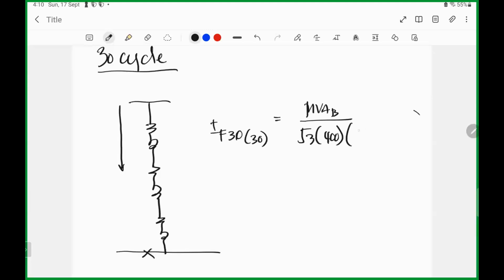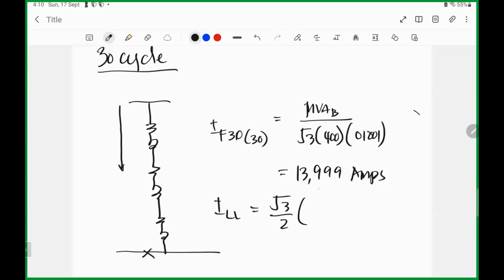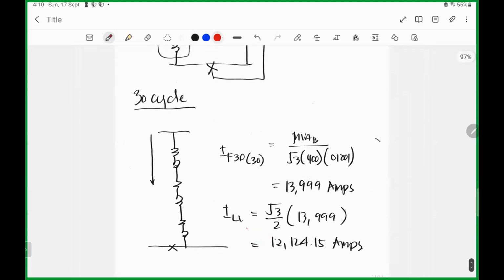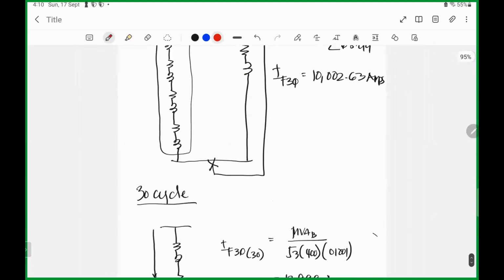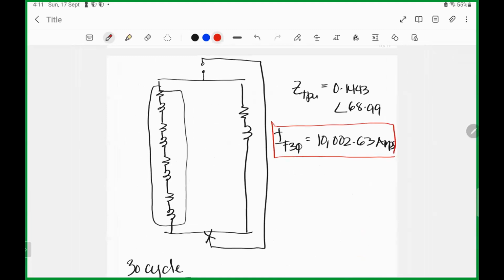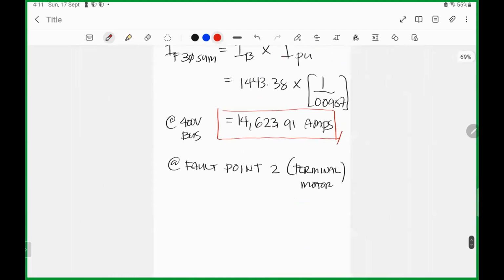Now, my total impedance will be now 0.1001, if I'm not mistaken. You can check this one na lang. But my fault current at 30 cycle is 13,999 amps. So my I line to line is simply square root of 3 over 2, or 87% of my three-phase fault at 30 cycle. So this one will be 12,124.15 amps. Okay? So mamaya i-plot natin yan dun sa TCC. Kailangan kasi natin ng mga fault current sa TCC.